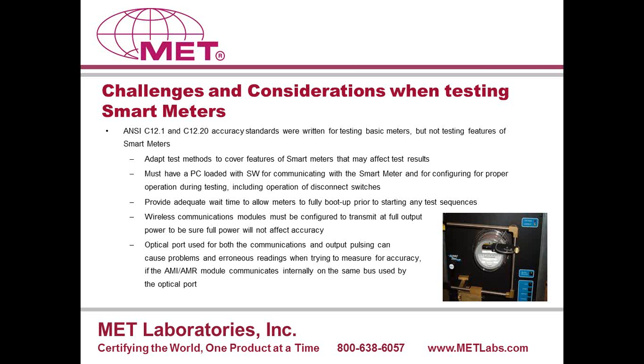I mentioned before the wireless communication modules. You need to make sure that they're tested at full output power to be sure that that's not going to affect accuracy. There are times when we've seen a module that's not set to transmit at full power not affect the meter's accuracy. However, when we set it to full power output, it can affect the accuracy. So we just want to make sure that when we run through our test program, it's a valid program and we've covered those bases. And I mentioned some of the communications issues that we see on the optical ports. Again, if you have communication on that same test port that we're using to measure the Kt pulsing, then we can essentially fool our test equipment into thinking that it's pulsing rather than just simply communication between the module and the meter. That's going to throw the accuracy off tremendously.